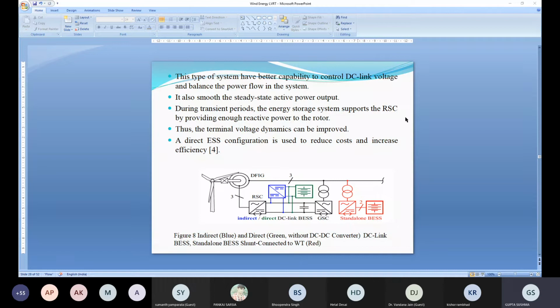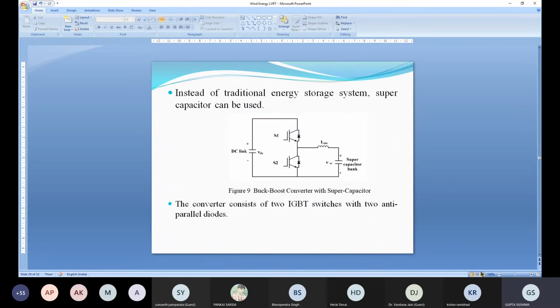Next, we can use a super capacitor also instead of this energy storage system. We can use a super capacitor for the fast dynamic response. It can operate with a buck boost converter. When energy is required in the DC link, it will discharge and maintain the DC link voltage. When the voltage is high over here, it can take energy from the DC link voltage and DC link capacitor and maintain it constant. The dynamic response is very fast, but this super capacitor is costly.